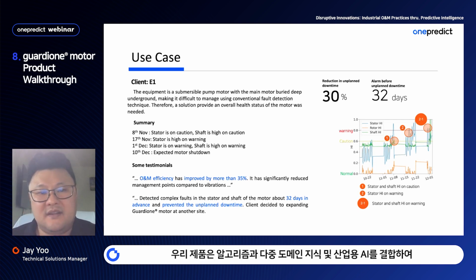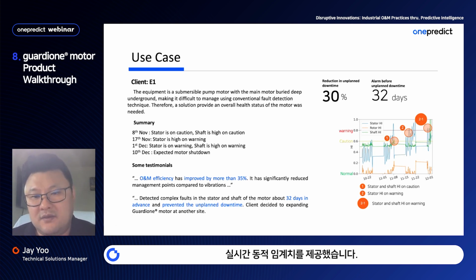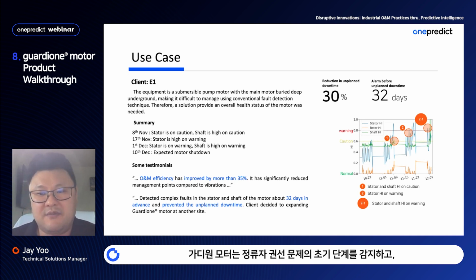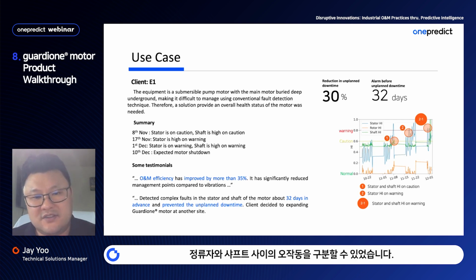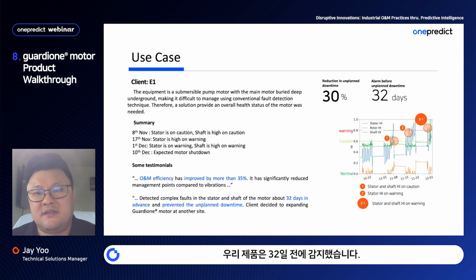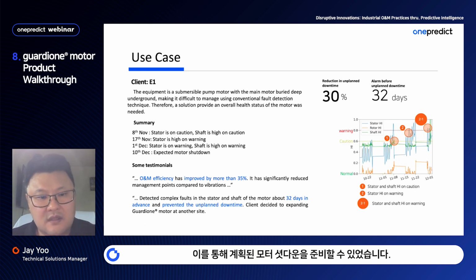By combining advanced algorithms, multi-domain knowledge, and industrial AI with a real-time dynamic threshold, the Guardione motor was able to detect the early stage of stator winding issues and distinguish fault modes between stator and shaft. Our product detected the issue 32 days in advance, allowing the client to plan for the expected motor shutdown.